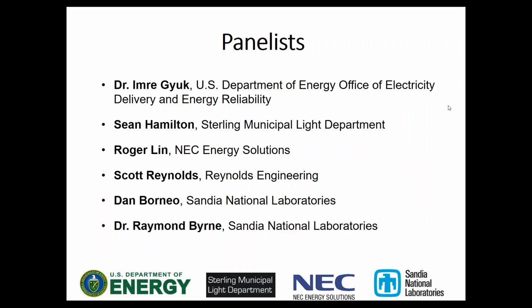So during that 30 minutes, the police station will be powered. Correct. The idea is based on, going back to Sandy, where a lot of times they couldn't get fuel for the generators. With the generators constantly full and maintained, they'd have operational time for the 15-20 minutes it takes to pull those cutouts. They would operate, and then at that point we could pick them up from there and conserve their fuel for the future.